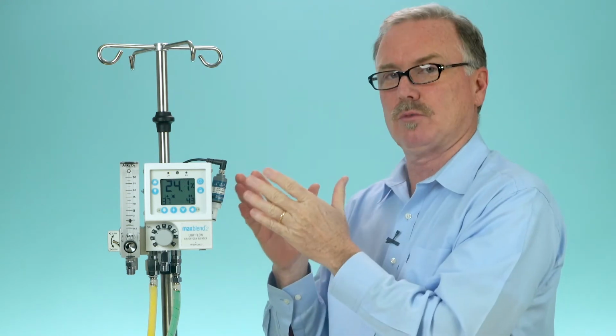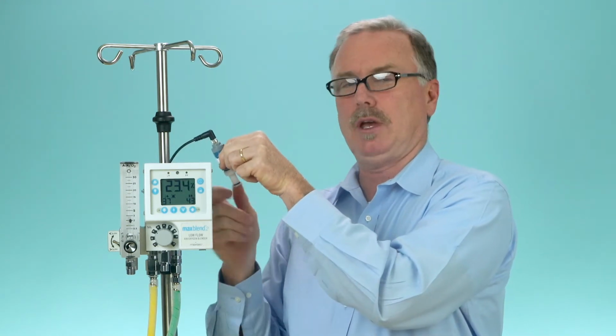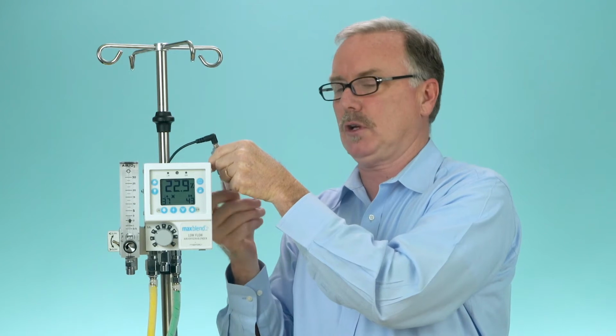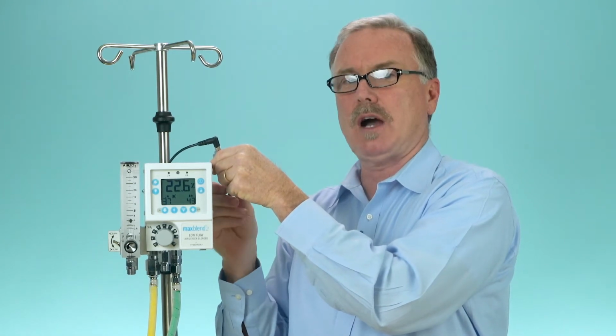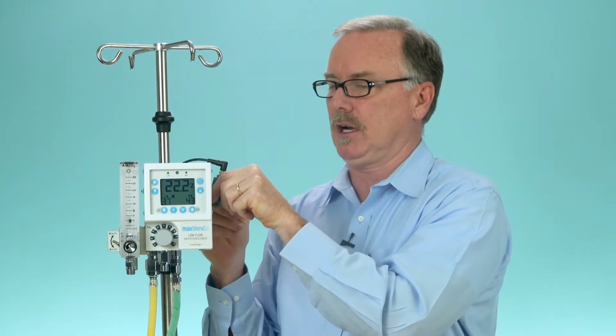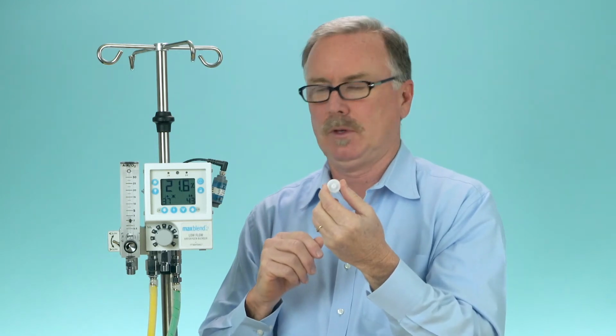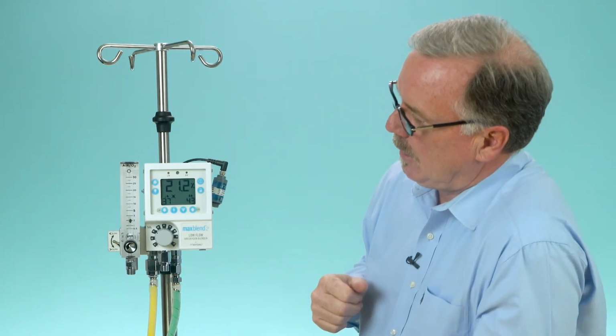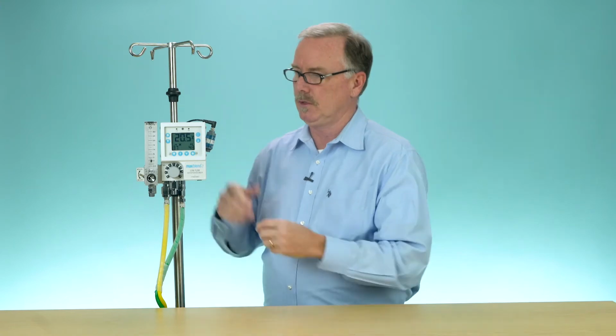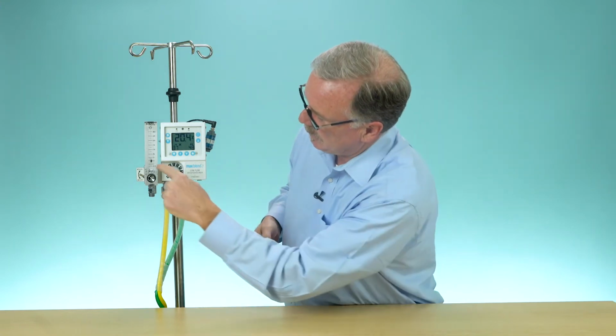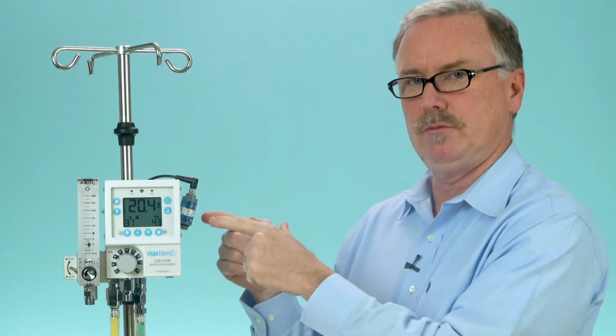Now, if you want to speed up the process of getting this into a room air environment, we would recommend removing this diverter, because there could be small amounts of oxygen or a mixture of oxygen and air trapped in our diverter. So that speeds it up. So I can assure you, as long as I don't have any other device running in this area, that fuel cell is being exposed to room air. Notice I'm still delivering the 2 liters of the 40%. Nothing's changed. I just moved it.